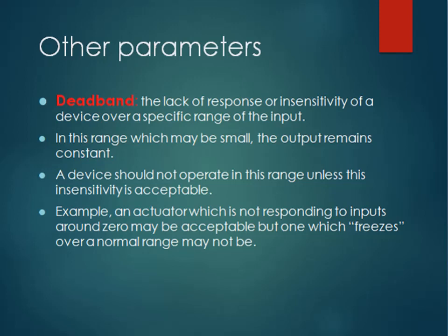There are certain other parameters also, like deadband: the lack of response or insensitivity of a device over a specific range of the input. In this range, which may be small, the output remains constant. So the device should not operate in this range unless this insensitivity is acceptable. For example, an actuator which is not responding to input around 0 may be acceptable, but one which freezes over a normal range may not be.